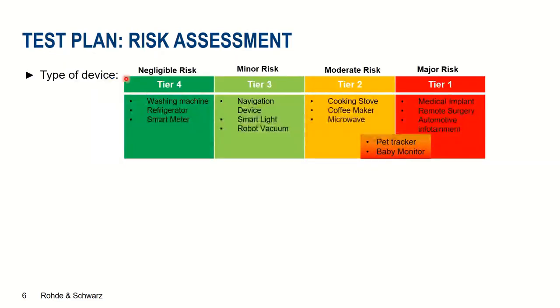We have a tier-based system where we categorize risk. The risk is defined by whether a wireless coexistence failure causes bodily harm to the user. If yes, those are more risky products categorized in higher risk tiers — Tier 1 being the highest. Tier 2 is for slightly less risky products, and Tier 3 and Tier 4 are the less risky ones.